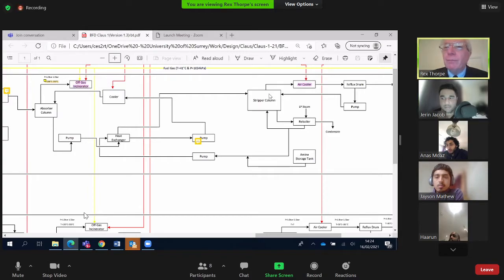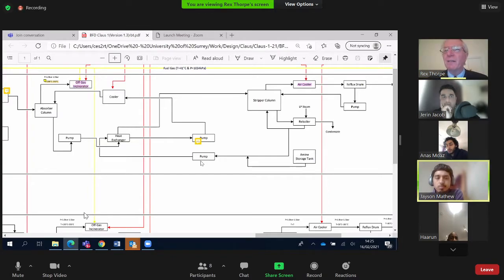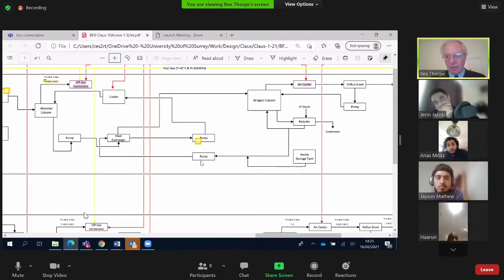Well, you don't need a pump every time you get a pressure change of 0.2 of a bar, particularly not when you've just pumped the pressure up here - why would you pump it up again? This is pumping for pumping's sake. You only have as many pumps as you need, you don't have extra pumps. So I don't think you need either of those actually.